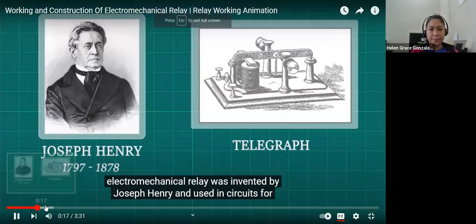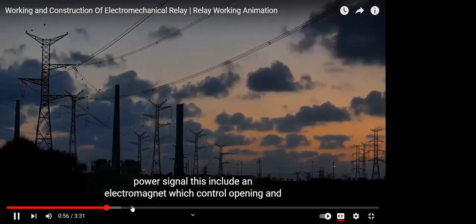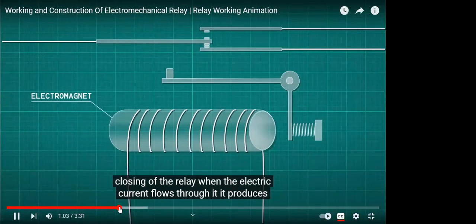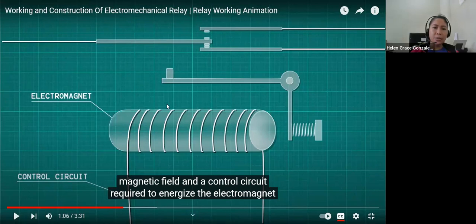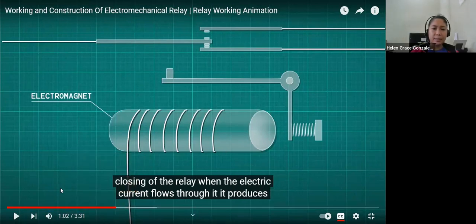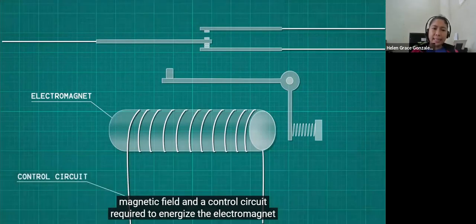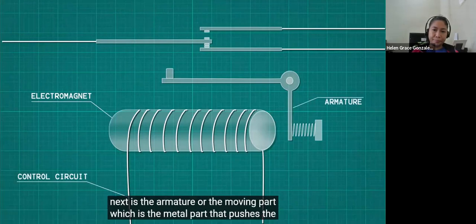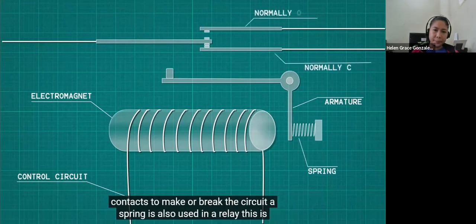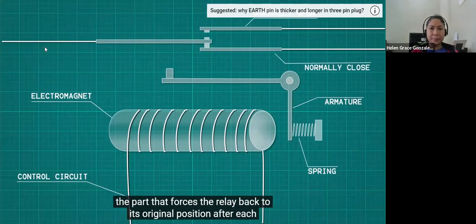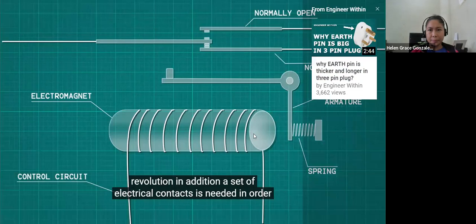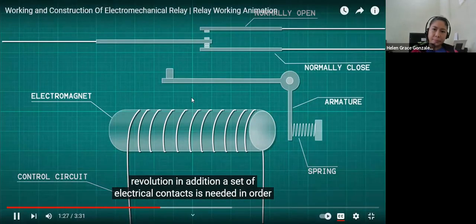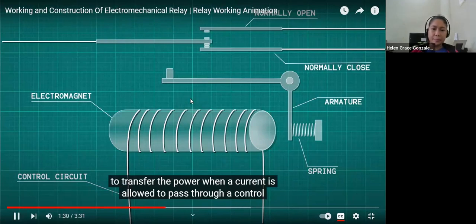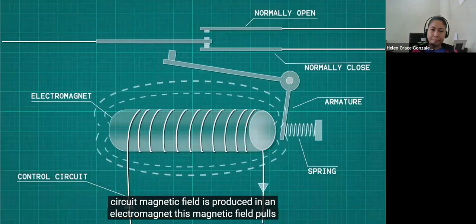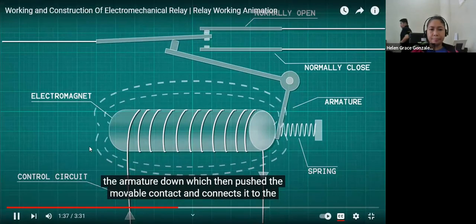Even today, relays are operated by voltage, current or signal, which produces a magnetic field and a control. In an electromechanical relay, when electric current flows through it, it produces a magnetic field. It has an electromagnet, and a control circuit is required to energize the electromagnet. Next is the armature, or the moving part, which is the metal part that pushes the contacts to make or break the circuit. A spring is also used in a relay. This is the part that forces the relay back to its original position after each operation. In addition, a set of electrical contacts is needed in order to transfer the power. When a current is allowed to pass through a control circuit, a magnetic field is produced in the electromagnet. This magnetic field pulls the armature down, which then pushes.